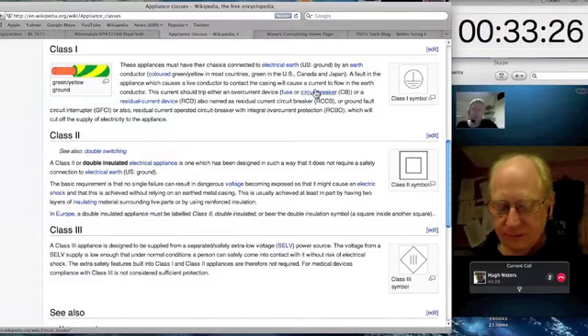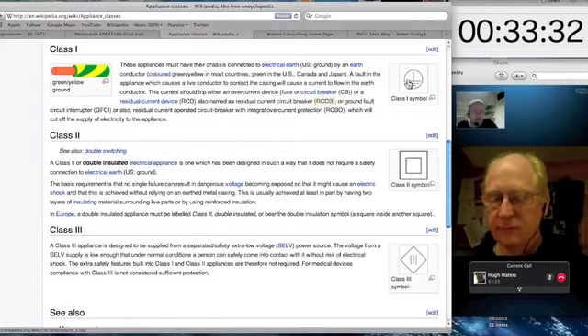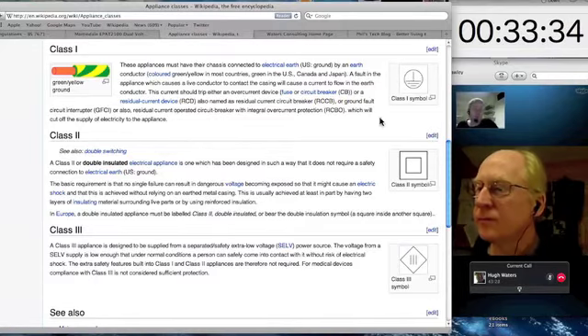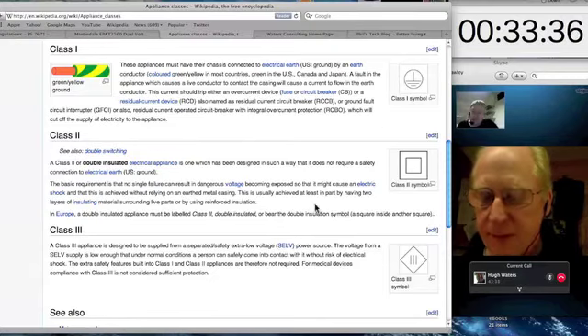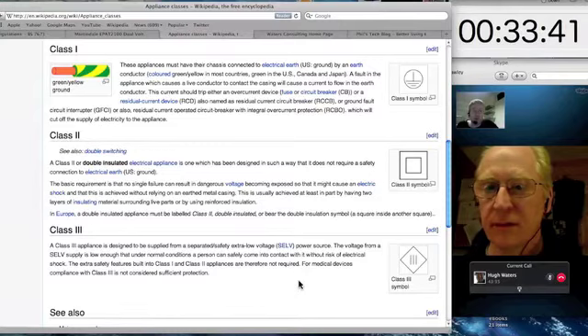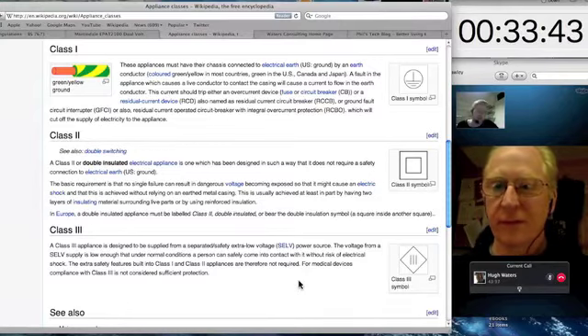And Class 1 pieces of equipment are those things which are metal cased, with high voltages inside, and by extension they need an earth, and you can see the earth is part of the Class 1 symbol. Now there is Class 3, but that's for low voltage equipment used medically, typically equipment used in operations and things like that, and so that doesn't really concern us. We're generally not going to come across that.